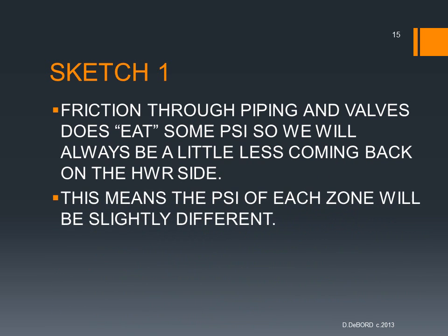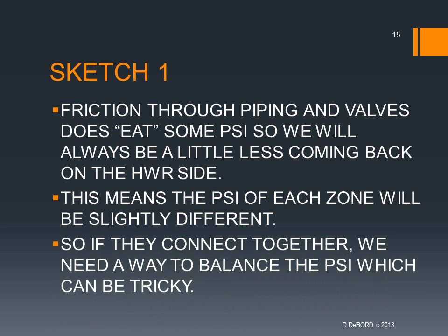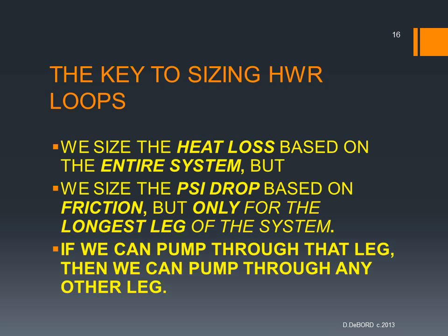But we have another consideration: friction. And friction through the piping and the valves takes away some of the pressure. So it was always going to be a little bit less coming back on the hot water return side than it was on the hot water supply side. This means the pressure for each one of those 3 zones will be slightly different because they all had different size loops, less piping and more piping, so they're going to have more or less pressure loss. So if we connect them together, we need a way to balance the pressure, and this could be tricky.